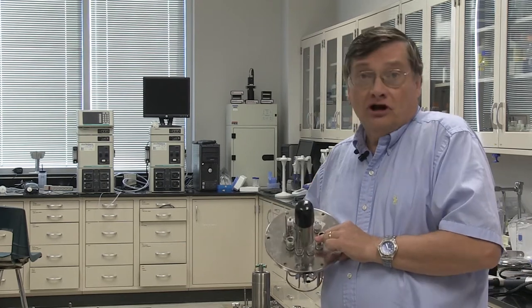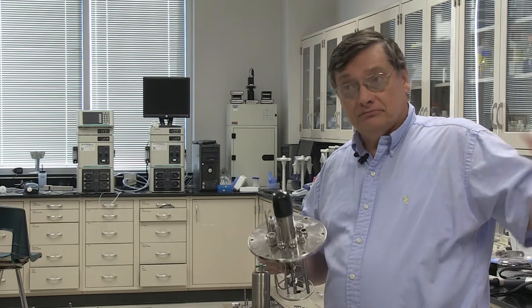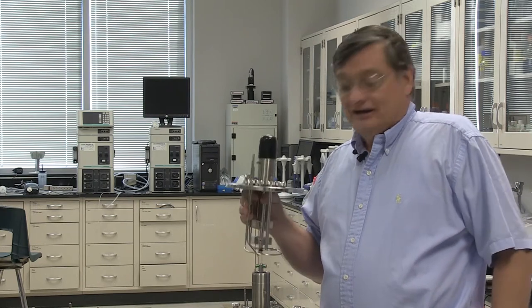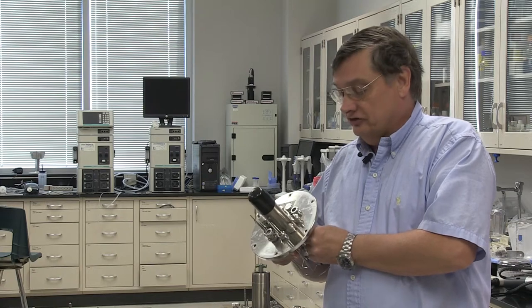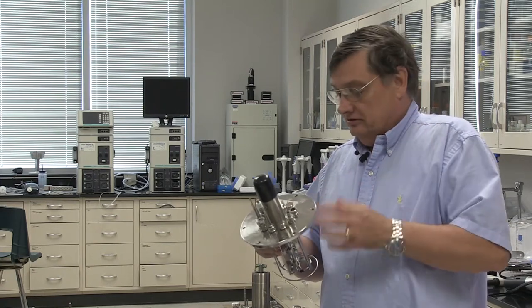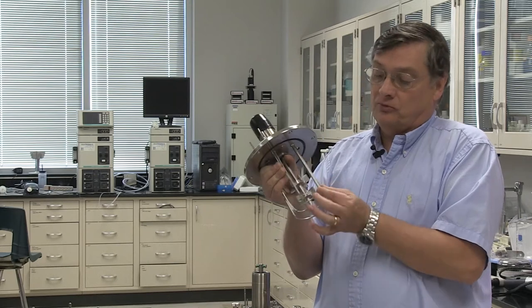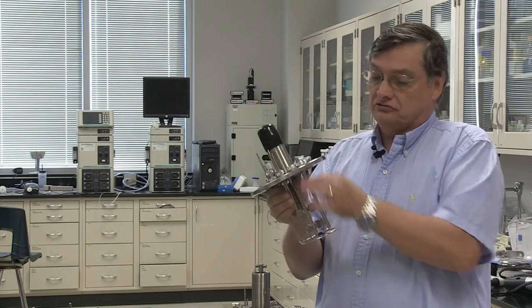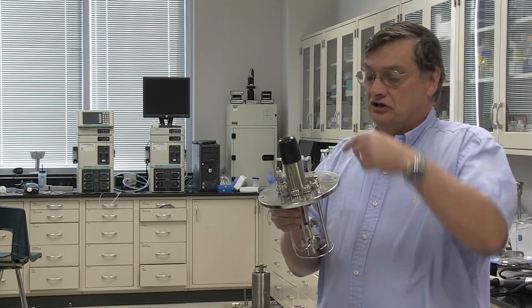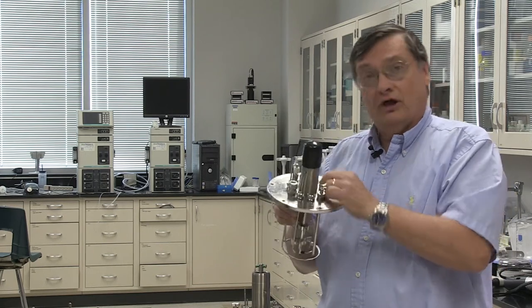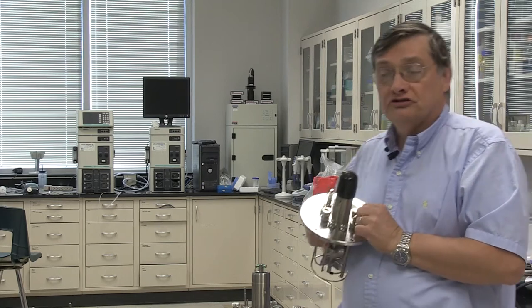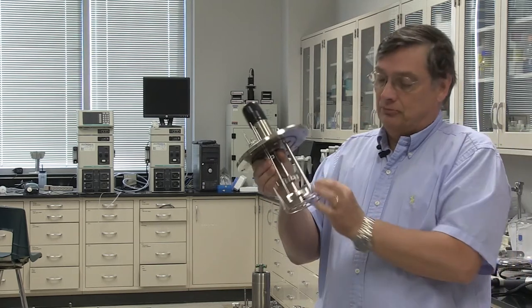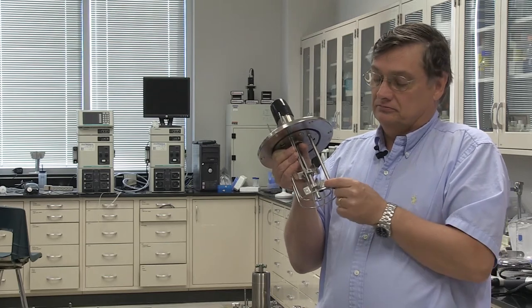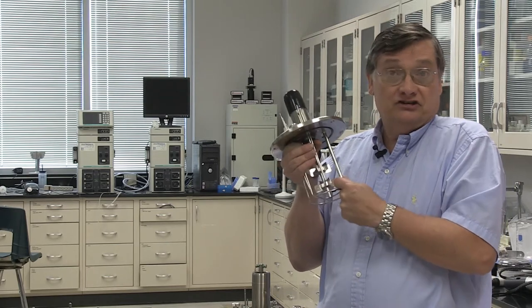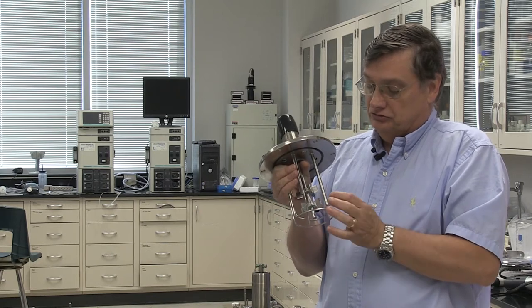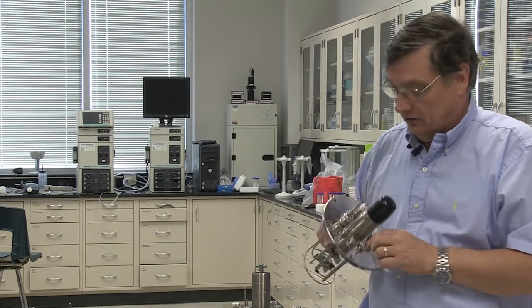The thermocouple cannot be autoclaved. So it's kept away, or not placed in the vessel, for its autoclave. So since it's not going to be sterile, it has to be in a closed system. So this thermal well is a sealed tubular container so that the thermocouple will actually be inserted in it. And we'll have to add a little glycerin in there to allow the temperature convection to get to the thermocouple to tell the temperature. So that's the thermal well.